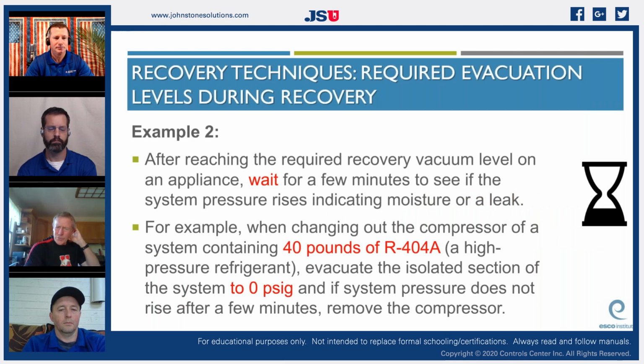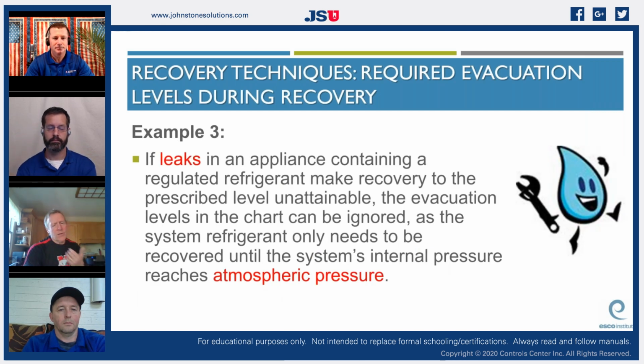Always remember this, no matter if you're doing residential or commercial: after you reach the required vacuum level, shut it off and wait for a few minutes to see if system pressure rises. So you're looking for whether there are still non-condensables in there or if it actually has a leak. If it has a leak, it'll go back up to atmospheric pressure, which is 14.68 psi per square inch, I think. So you will eventually work your way out of a vacuum completely if there is a leak. Mm-hmm. Don't use your suction gauge to tell you if it's a deep enough vacuum or if it's got a leak, by the way.